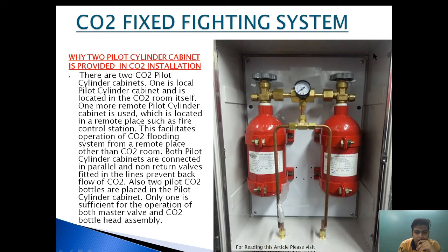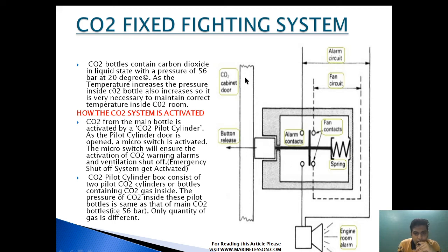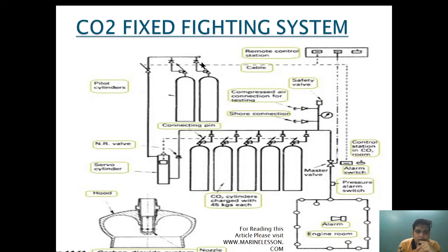The door of the CO2 pilot cylinder is provided with an alarm contact. When the door is closed, the alarm contacts are not connected. When the door is opened, through a spring mechanism this contact will be made. As soon as the alarm contact is made, an alarm circuit activates and an engine alarm indicates that the CO2 pilot cylinder door has been opened. The fan contact will also be disconnected and the fan of the engine space will be switched off.